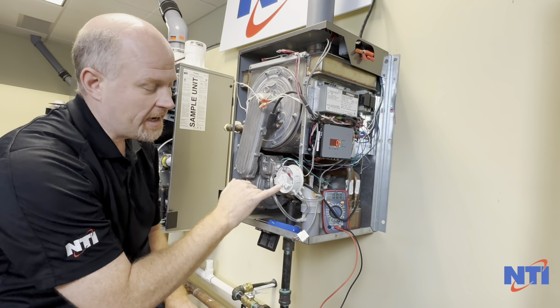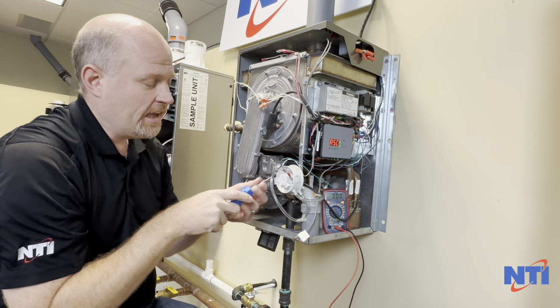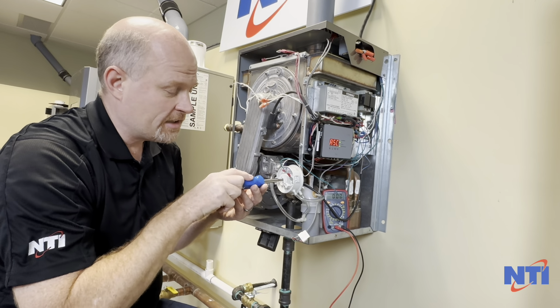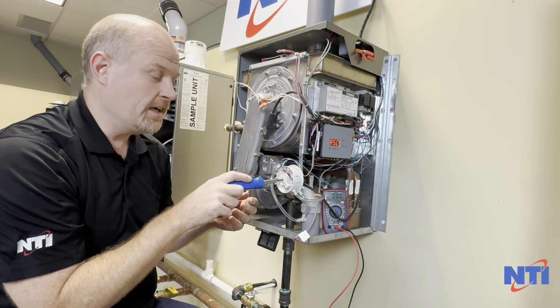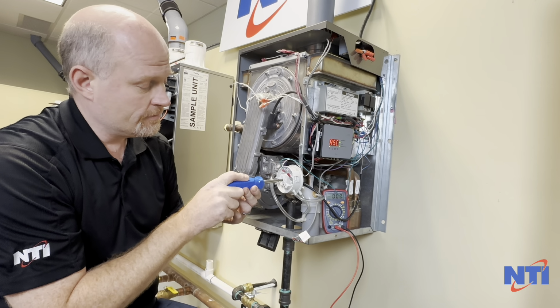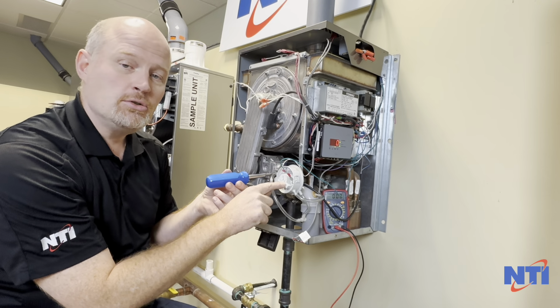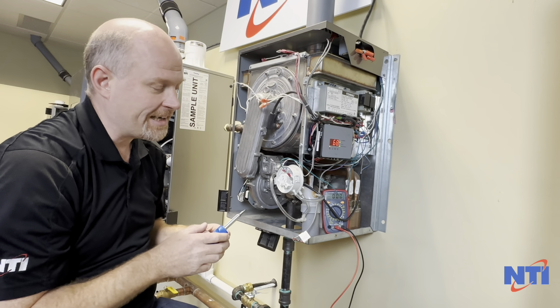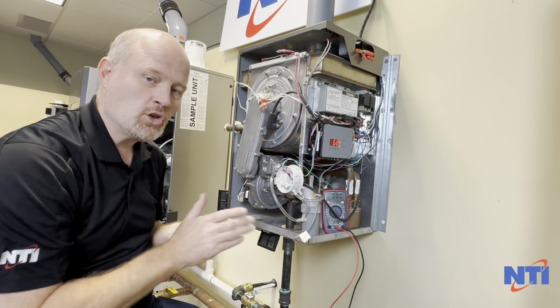Now, you'll want to inspect the setting here, the little black square, and these are adjustable. If somebody's been playing with this and they've adjusted it down to the black square, that actually closes the switch permanently, and you're going to get a problem. So you'll want to make sure that you adjust this dial to where this little arrow points to the number 2 in inches H2O. That is the correct setting and where it must be for safety. You can set it a little higher than that, but you should not set it lower.